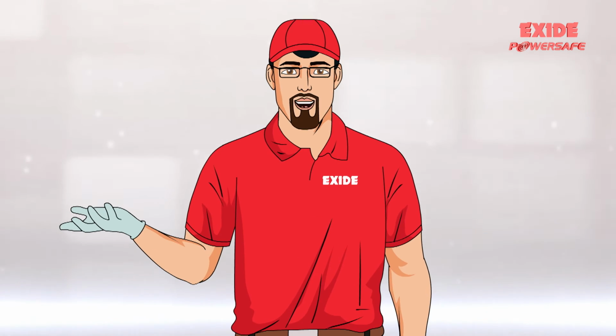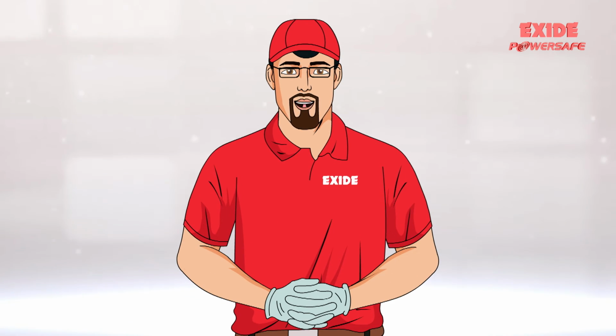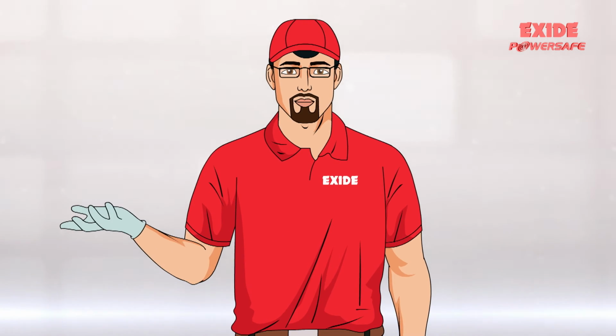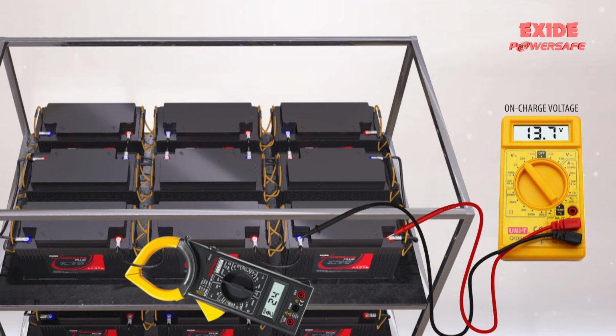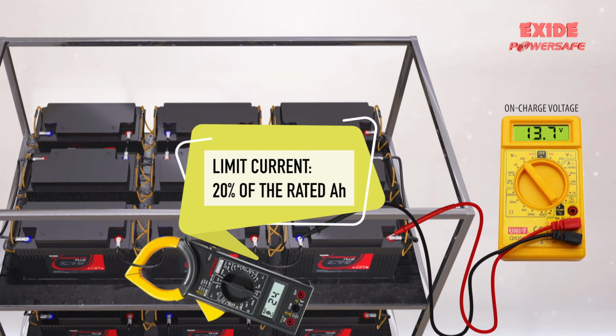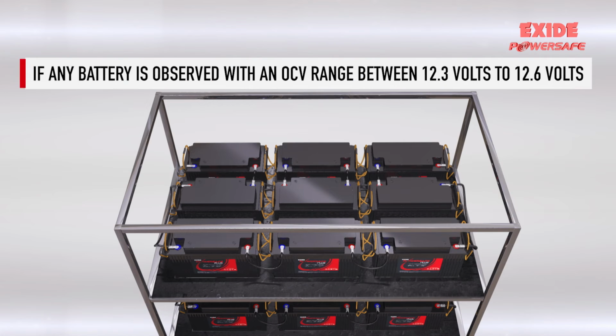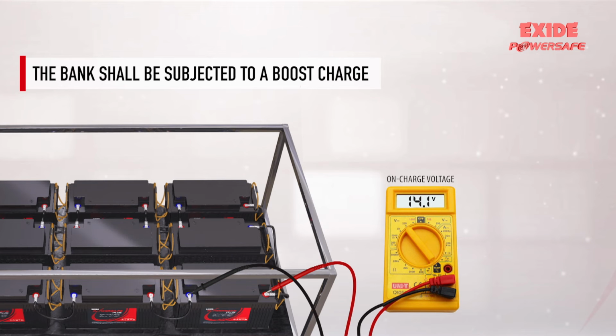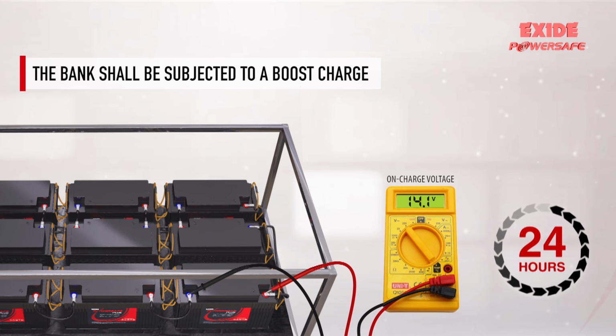Commissioning of the same is a very important step. The following points will help to ensure that the commissioning has been done correctly. Always subject the batteries to a commissioning charge of 13.7 volts with a limit current of 20% of the rated ampere hour for 72 hours without connecting the load. For the installation where one or more batteries were observed with an OCV range between 12.3 volts to 12.6 volts, the bank shall be subjected to a boost charge of 14.1 volts for 24 hours, followed by the mentioned commissioning charge regime.